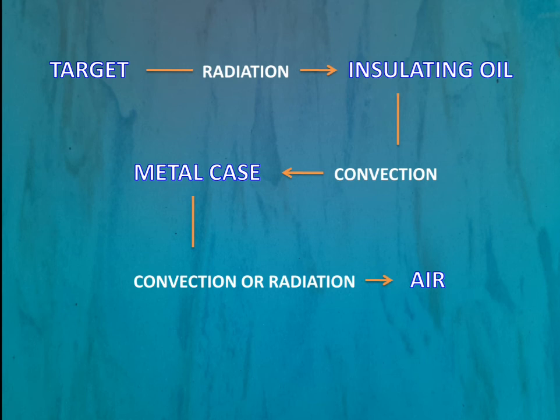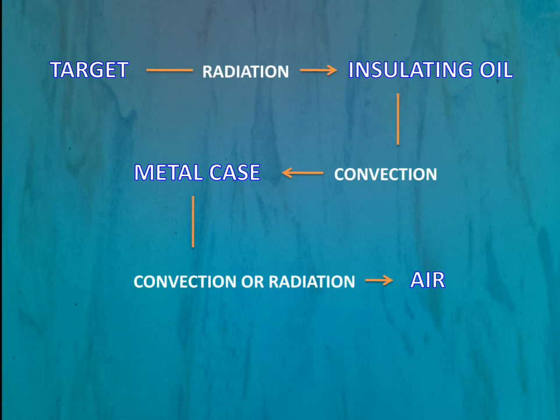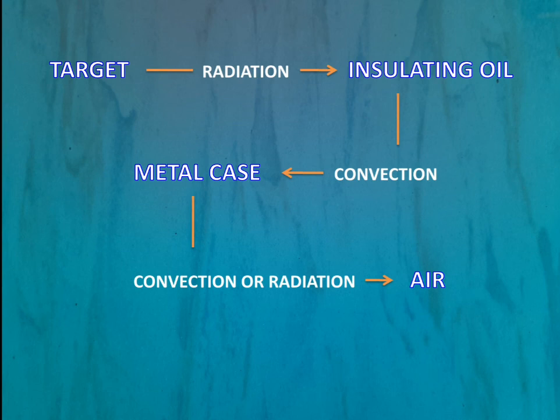Looking at this flow chart: from the target area, heat is transferred to the insulating oil by means of radiation. We know the glass envelope is placed inside a lead case filled with insulating oil, which acts as both a coolant and electrical insulator. From the insulating oil, heat is transferred to the metal case or lead case by convection. From the metal case, heat is then transferred to air by convection or radiation.